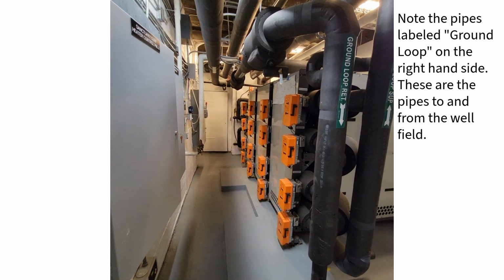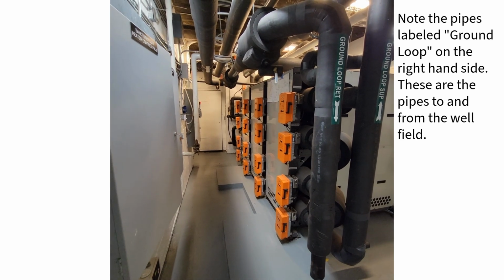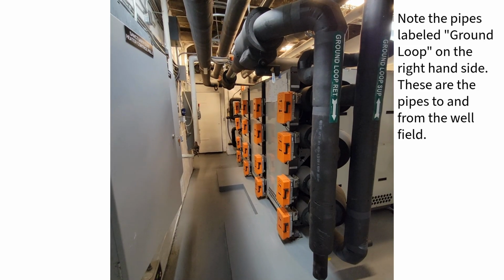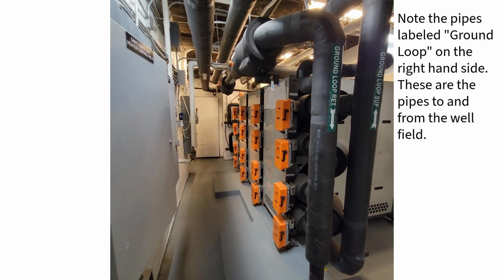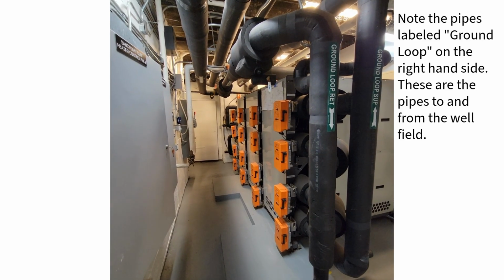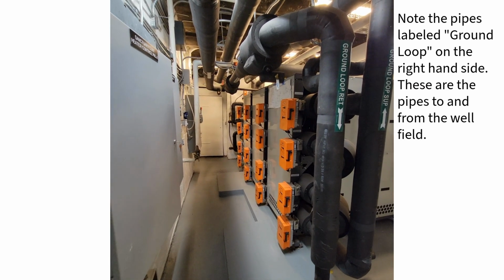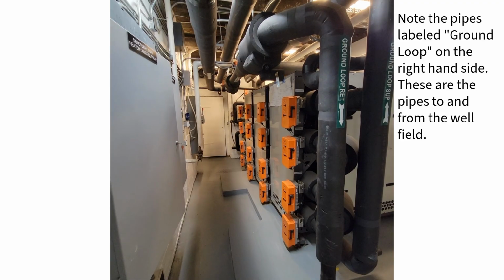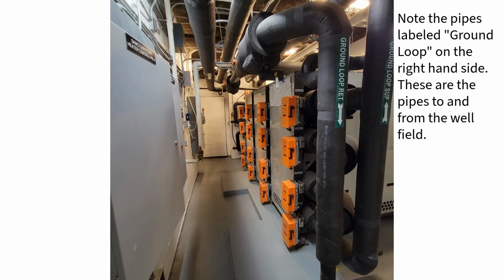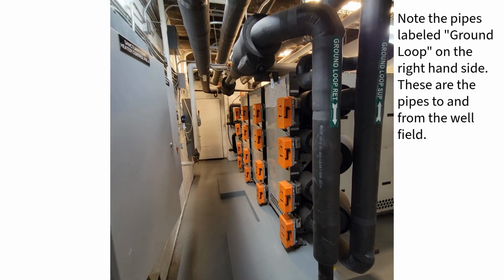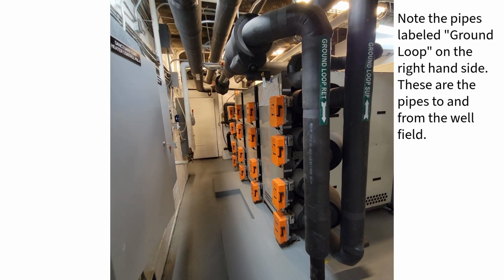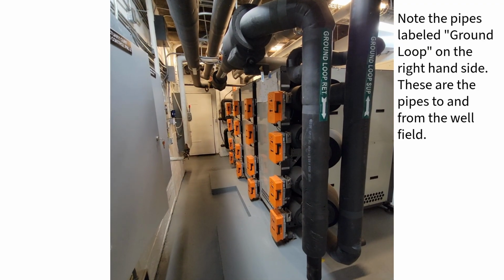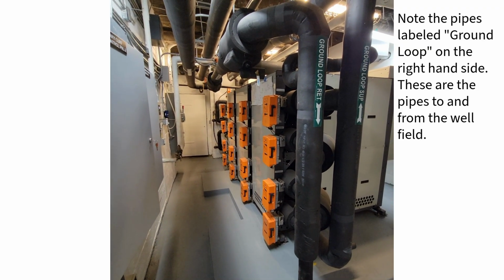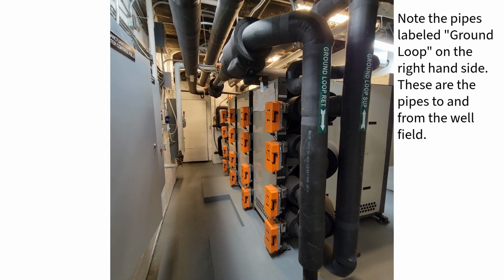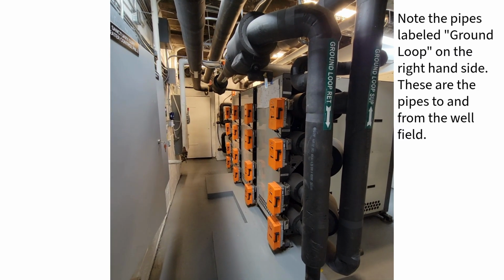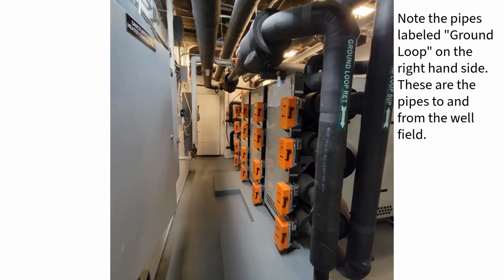This is the other side of the heat pumps. You can see the orange boxes are motor controllers for all the valves that send the hot and cold water to the appropriate heat pump, so we can direct the cooling water from the ground wells to the proper heat pump, and the output, hot water or cold water or both, because we can heat and cool in the spring at the same time. We can heat rooms on the north side of the building and cool rooms on the south side. These orange valves are all directed by the building management system to send the right temperature water to the right places.